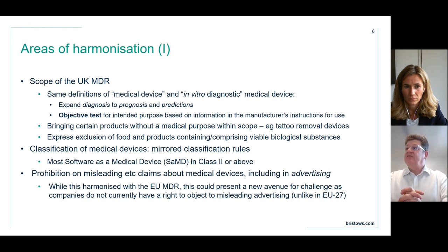The classification of medical devices mirrors the classification rules in the EU MDR. By way of example, virtually all software is a medical device, and we use the acronym SAMD. Virtually all of it is going to be classified class 2A or above. That was a big issue with the EU MDR when it first came along.